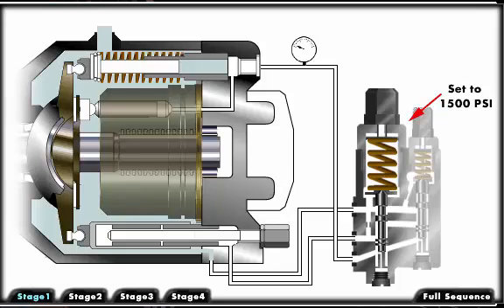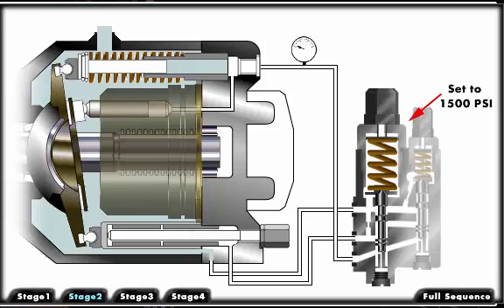In this example, we have used a pressure compensated piston pump. It is helpful to understand the functionality of a piston pump. If you need to review this, return to the pumps menu and go to the animation for the piston pump. As the pistons rotate around the shaft and follow the angle of the swash plate, they are pumping fluid out the outlet, which provides flow to move a component such as a cylinder.